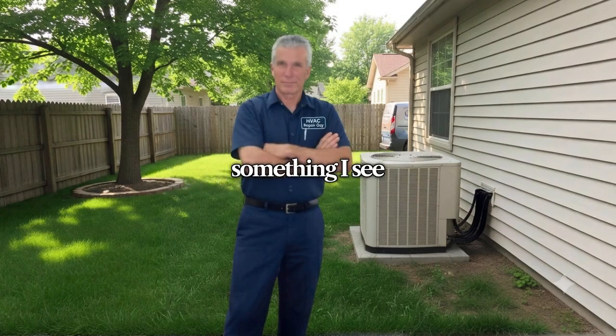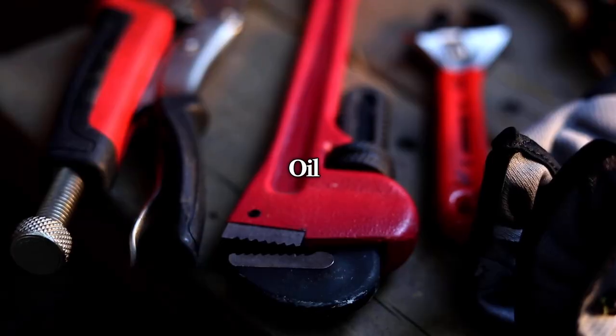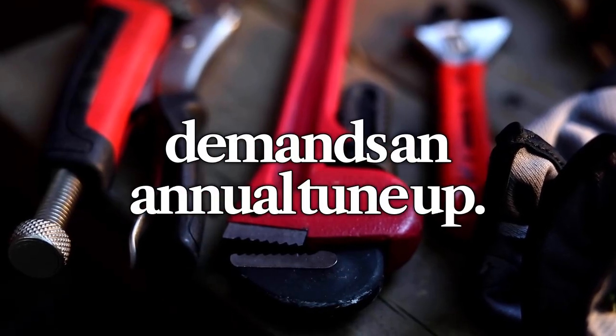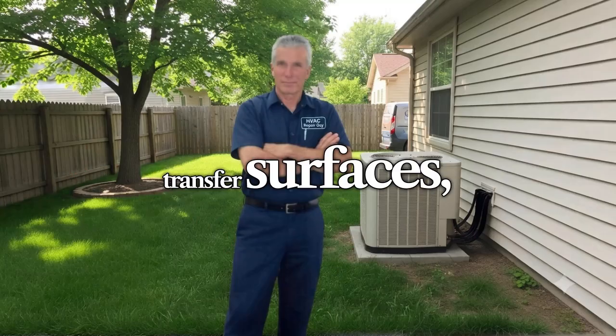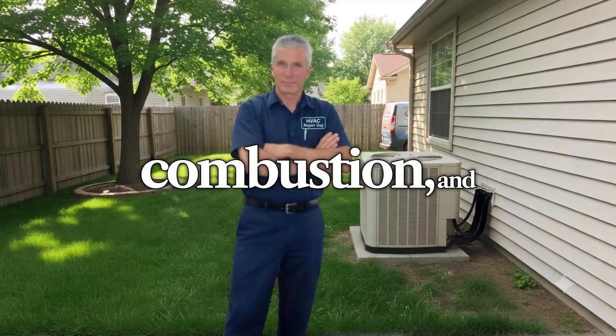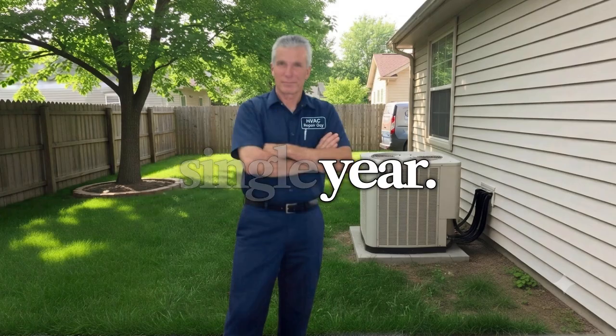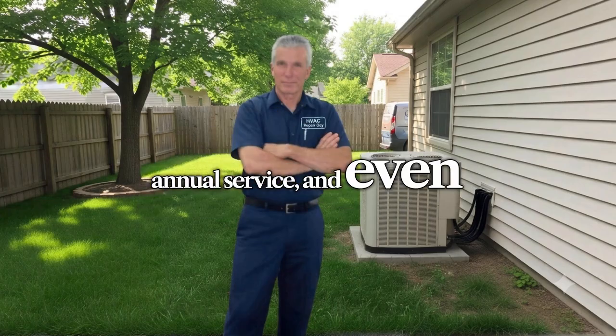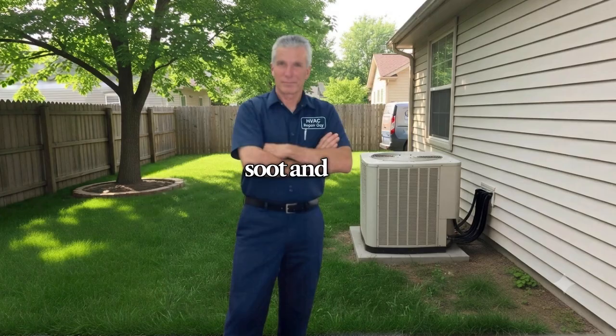Here's something I see homeowners misunderstand all the time: they look at a warranty length and assume it means maintenance-free operation. It doesn't. Oil-fired equipment demands an annual tune-up. You've got to clean the heat transfer surfaces, replace the nozzle, adjust the combustion, and check the safety controls every single year. Neglect that annual service, and even the best heat exchanger will choke on soot and lose efficiency.